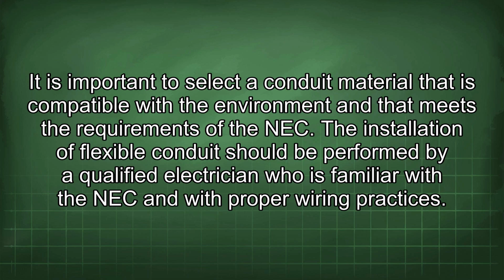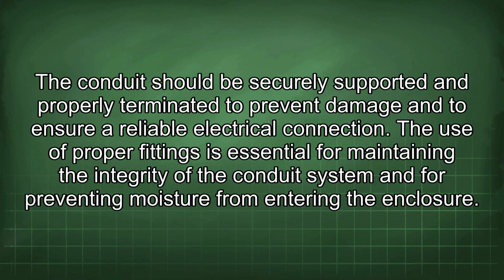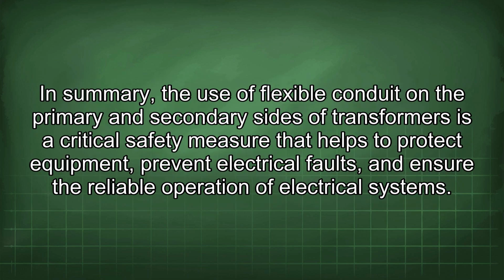of the NEC. The installation of flexible conduit should be performed by a qualified electrician who is familiar with the NEC and with proper wiring practices. The conduit should be securely supported and properly terminated to prevent damage and to ensure a reliable electrical connection. The use of proper fittings is essential for maintaining the integrity of the conduit system and for preventing moisture from entering the enclosure.